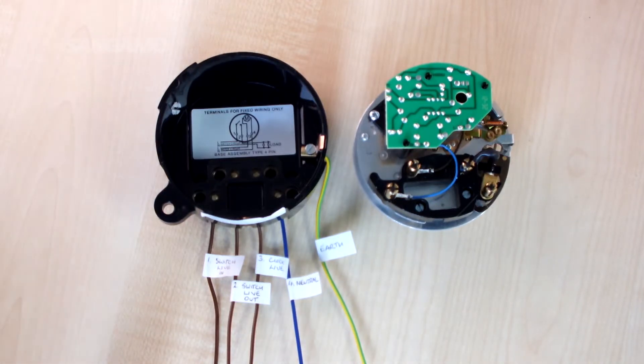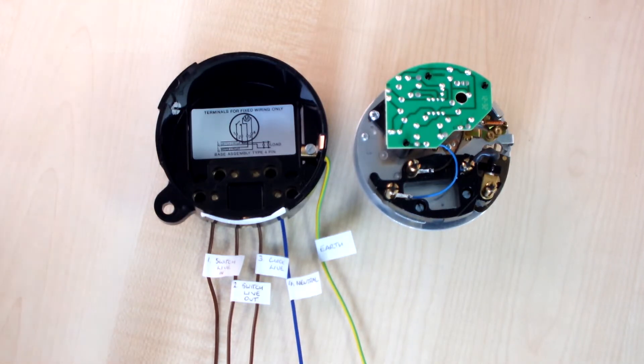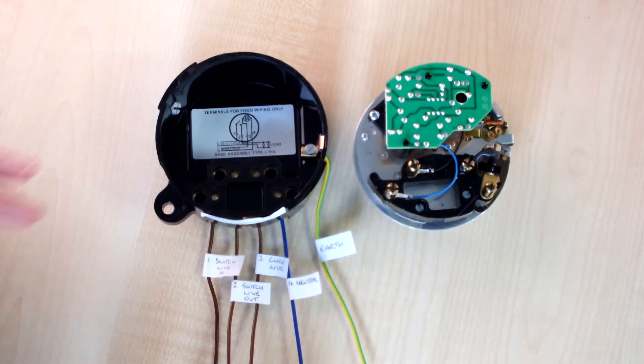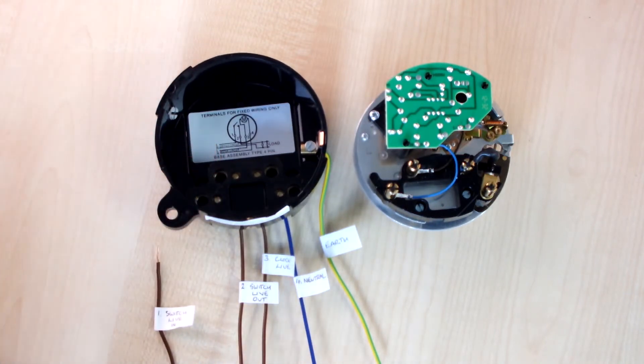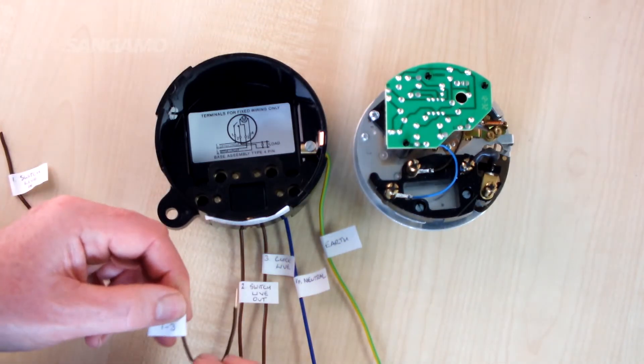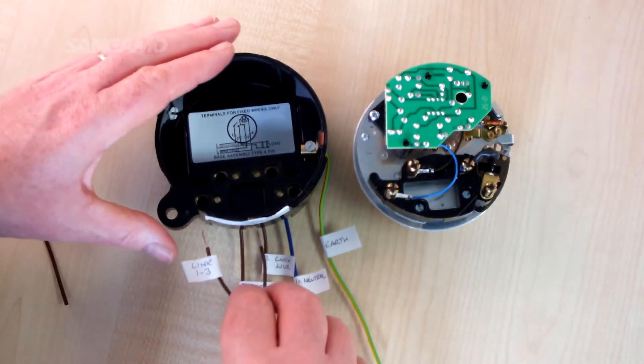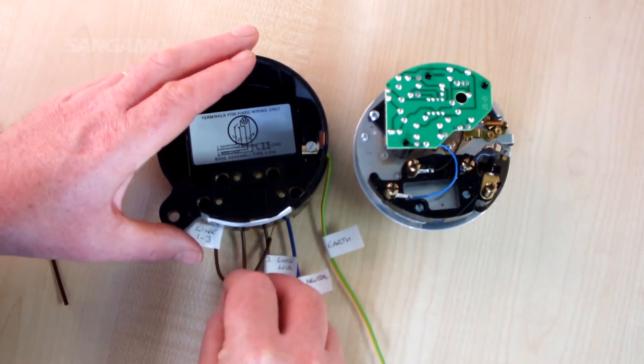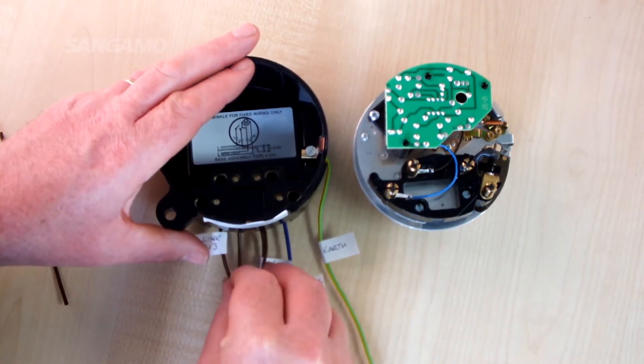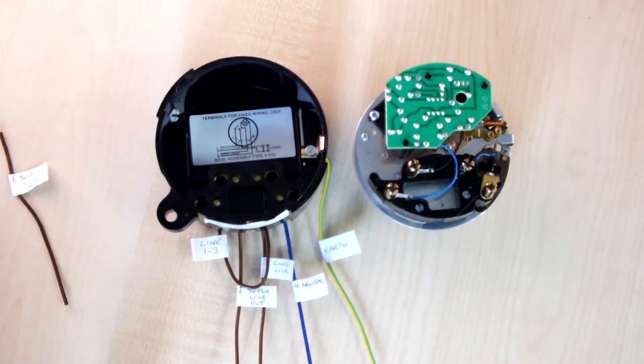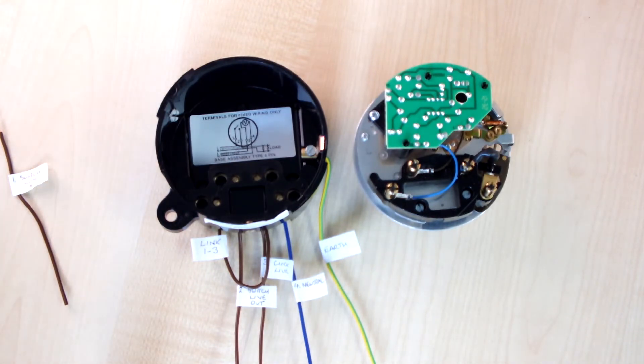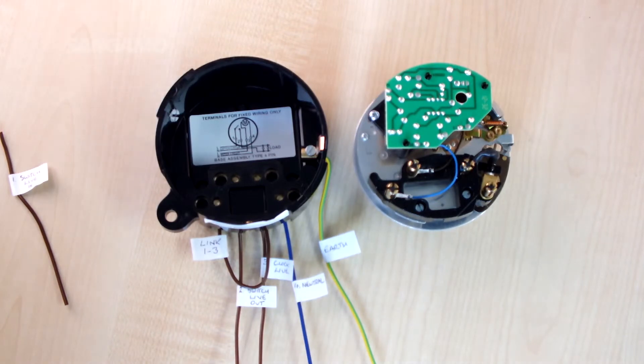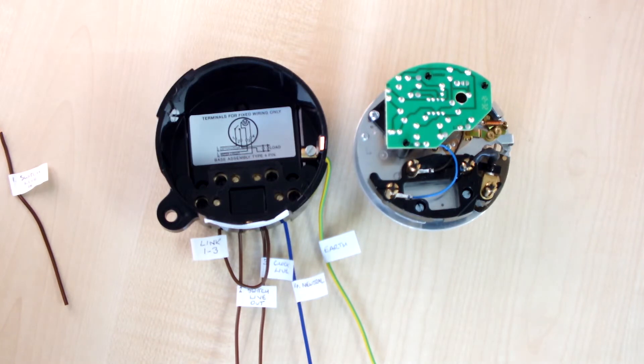If you have a 4 pin device but only one supply, then one way to get around it is to fit a link. You wouldn't have an independent supply for the switching circuit, but instead you would link from the clock live through to terminal 1. So you'd link from terminal 3 through to terminal 1, and you're now using the same live supply that's being used for the clock for the switching circuit as well.